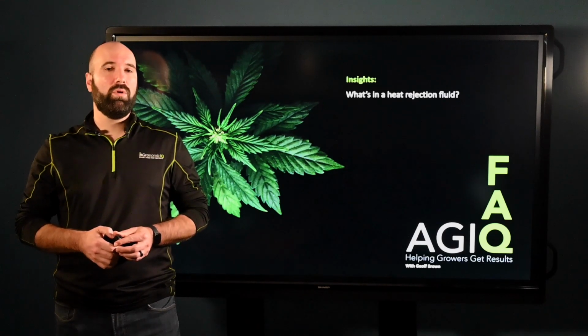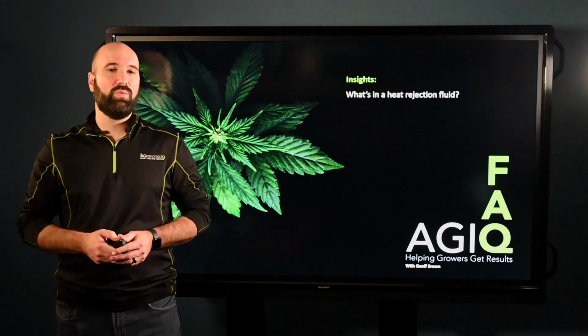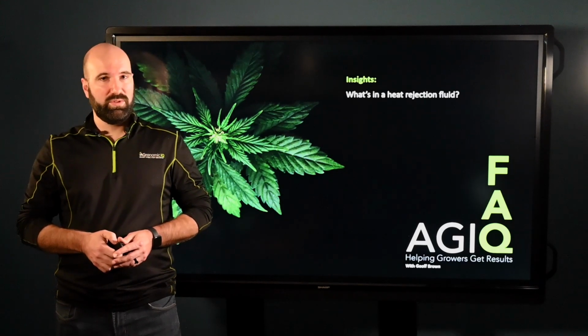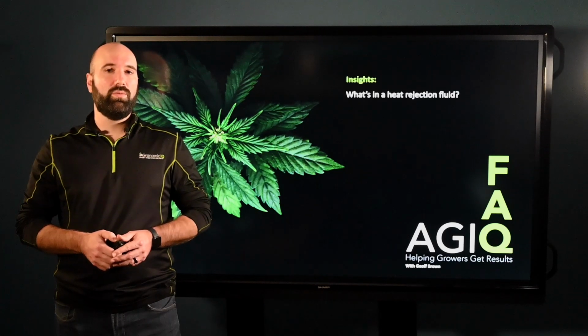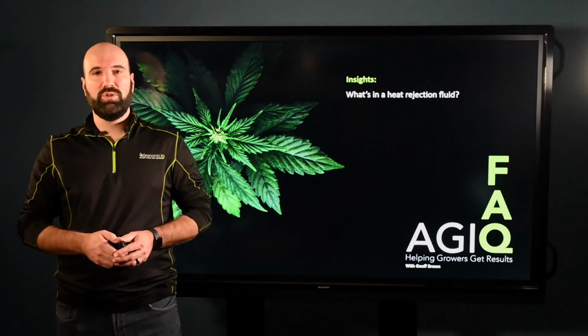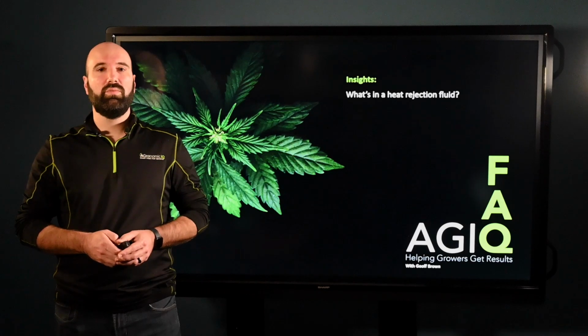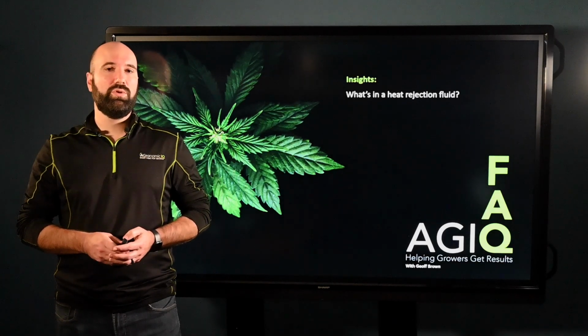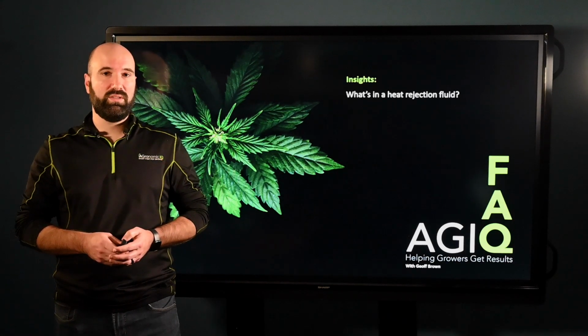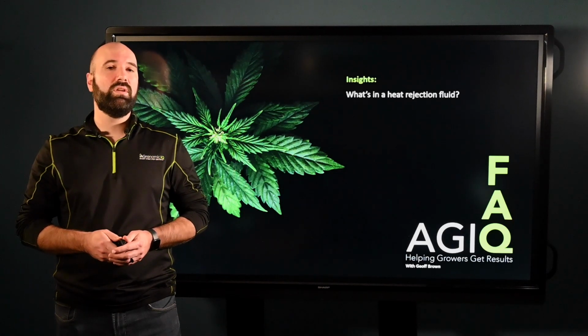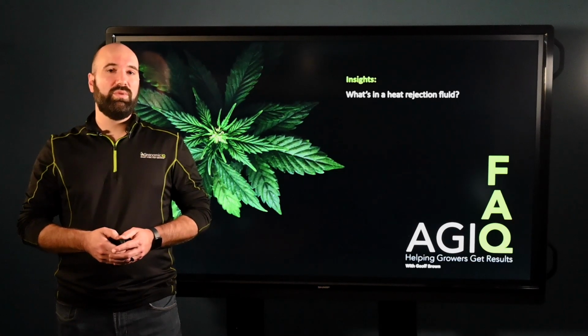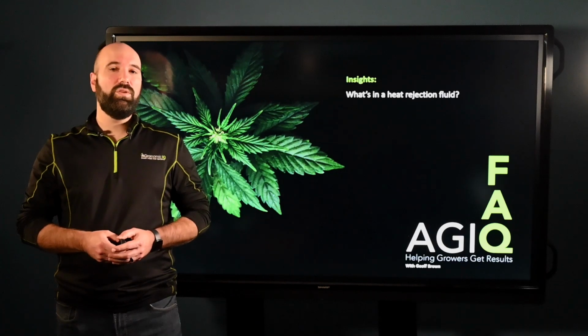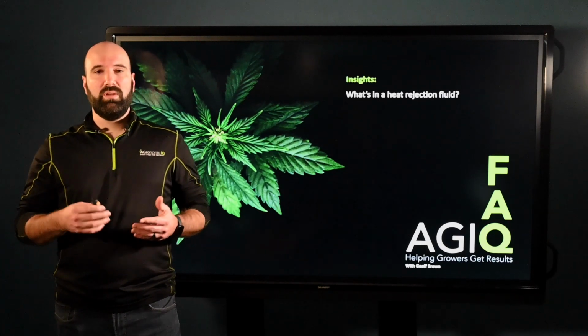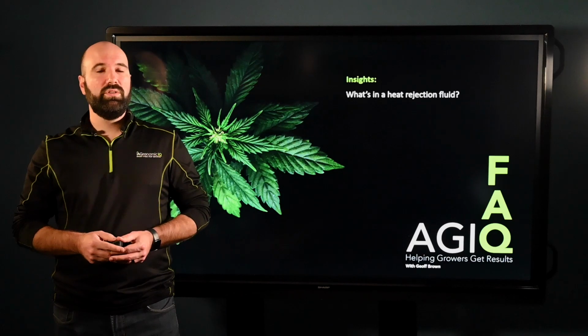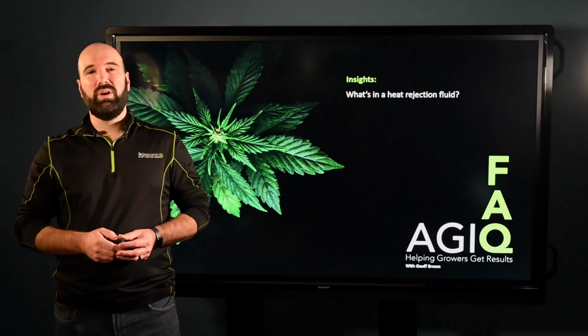So the larger your refrigeration system is, the more refrigerant you need. And refrigerant is expensive, and refrigerants go out of style. We're in the midst of a global warming potential reduction in refrigerant. That's going to force a refrigerant transition over the next 3 years and then over the next 7. Both of those are going to be very expensive in the future for maintenance. Even today, something like R22 is going for north of $100 a pound.